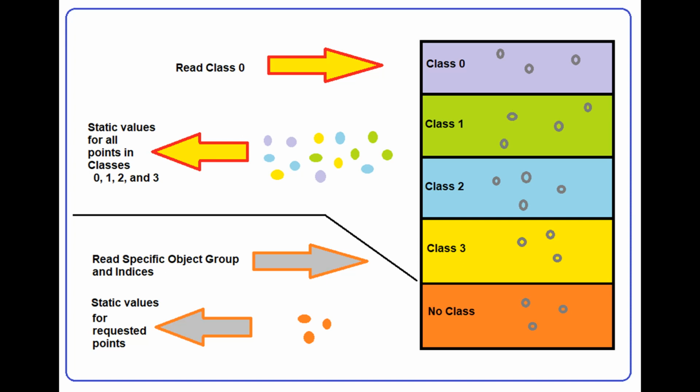Let's assume, for example, that some large outstation has 288 analog inputs. 256 of these contain real-time data, and the other 32 contain parameters. If all analogs were always reported in response to a class 0 poll, this would cause the 32 parameter points to be reported every time, wasting a lot of unnecessary bandwidth.